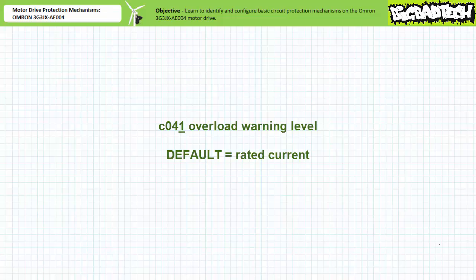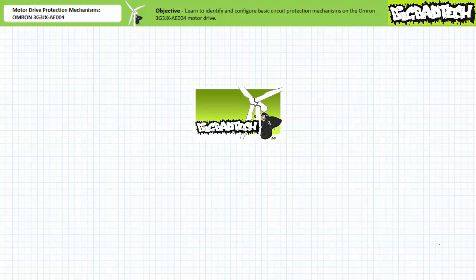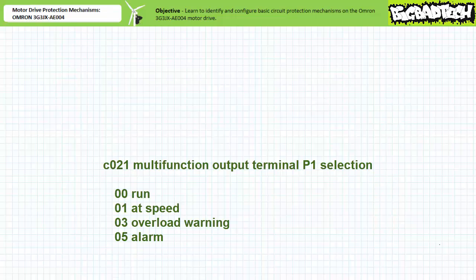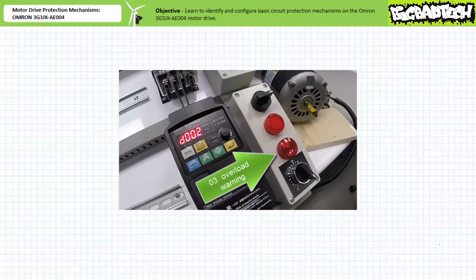The default setting for the OMRON 3G3JX AE004 motor drive overload warning level is the rated current. If one reduced overload warning level to something below the rated current, an operator or system could get an early warning of an impending overload and take the necessary precautions. We can change communication parameter C021, multifunction output terminal P1 selection, to 03 — overload warning. Given a properly sized unloaded motor, if we wire up a pilot lamp low side switched by multifunction digital output P1 and change C021 to 03 overload warning, this pilot lamp should not illuminate given C041 is at the default state of 2.6 amps.